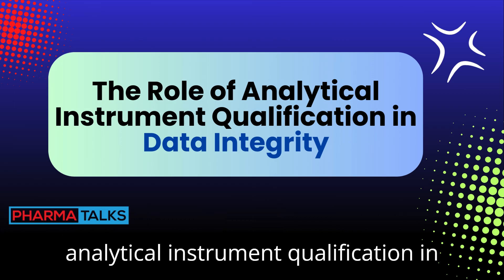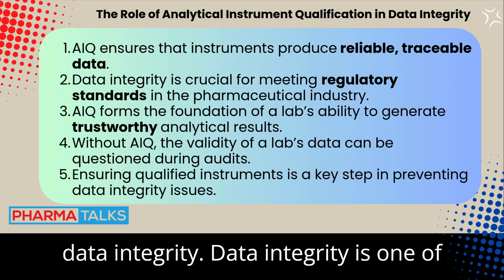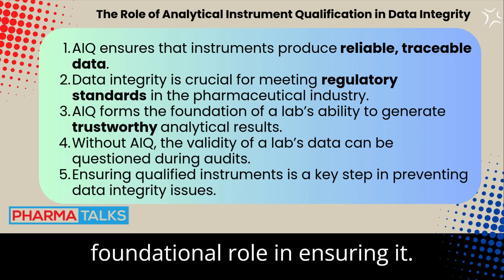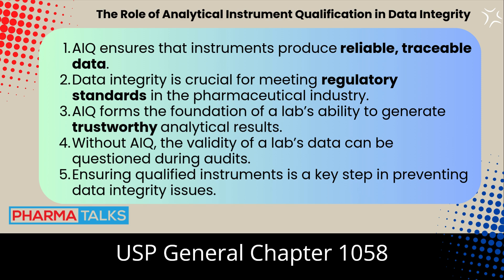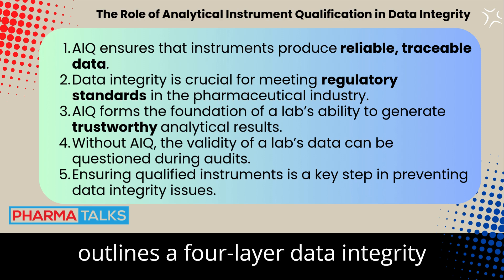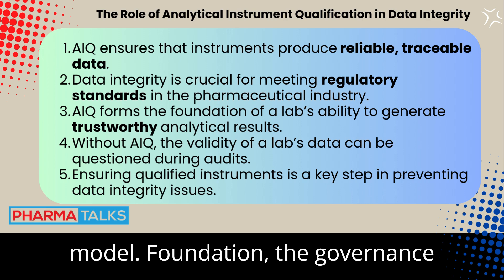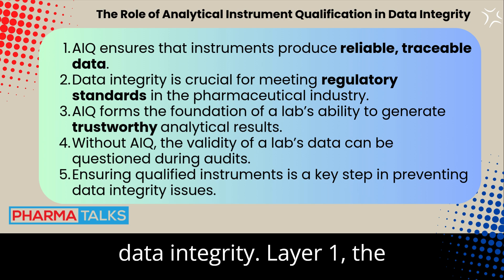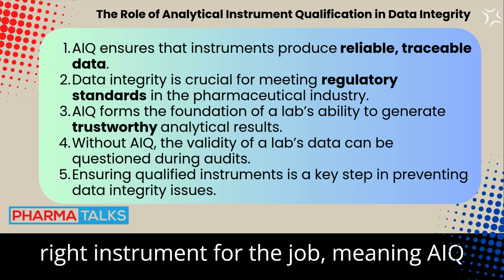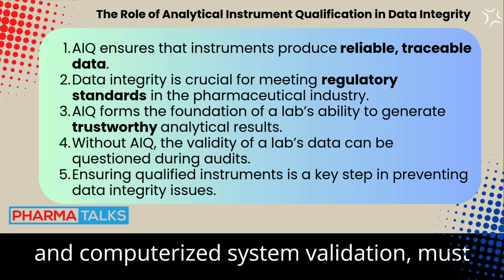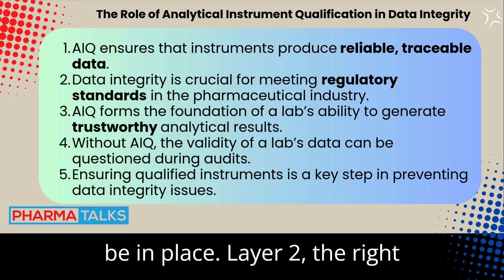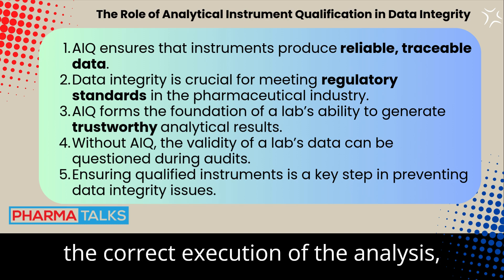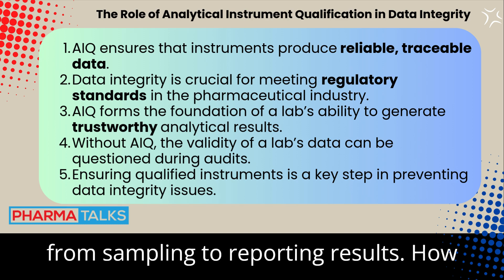Data integrity is one of the most critical aspects of compliance in regulated labs, and analytical instrument qualification (AIQ) plays a foundational role in ensuring it. USP General Chapter 1058 outlines a four-layer data integrity model: the Foundation covers the governance framework, policies, and training; Layer 1 is the right instrument for the job, meaning AIQ and computerized system validation must be in place; Layer 2 is the right analytical method, developed and validated under actual use conditions; and Layer 3 is the correct execution of the analysis, from sampling to reporting results.